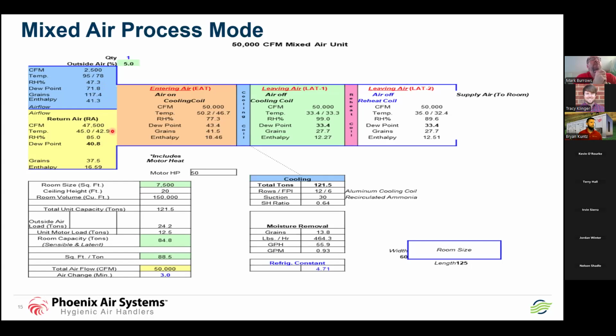Notice its temperature. This is typical, right? 45-degree dry bulb at an 85% relative humidity. Now we'll talk about the wet bulb at 42.9. The critical takeaway from this slide is the dew point of the room is 40.8 degrees. That means whatever we discharge into that space better be below that dew point, or what's going to happen? It's going to condense moisture on the ceiling.